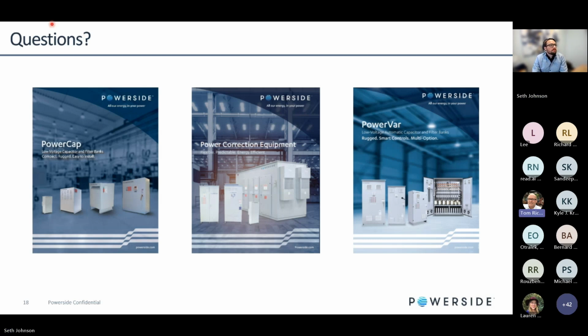Perfect. And I see a question just came in: are there plans for G5 up to 100th order harmonic monitoring? Obviously, we can certainly get into the discussion about harmonics above the 50th and supra harmonics in particular, that the PQube can do, especially picking up frequencies in the range of 2 to 150 kilohertz, which is what the new standards are requiring. So happy to take that offline with the monitoring group, or, Seth, if you want to go into supra harmonics right now, it is a topic that we're happy to answer.